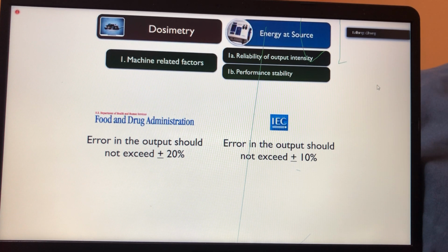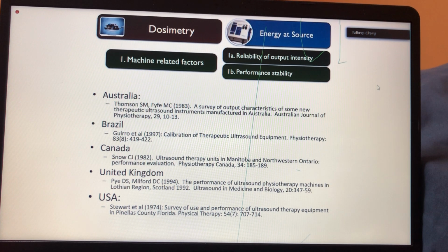Now, we know that for ultrasound, the FDA anyway, they are saying plus or minus 20% error. In Europe, they say plus or minus 10%. I think the FDA has now changed it to plus or minus 10%. So all machines that you buy must have plus or minus 10% error, no more than that. But we know from all the literature that's been done, I won't say none, most of the machines do not meet even that simple requirement. So if your machine is not reliable from week to week, whatever intensity is displayed on your machine is not reliable, then there's no way we can talk about dosimetry. There's no point talking about dosimetry. If you say 0.5 watts per cm squared is your setting, but 0.5 is not coming out of that transducer, then there's no point in talking about intensity.